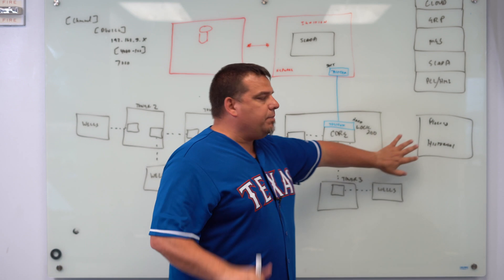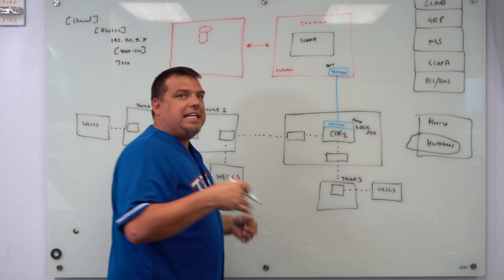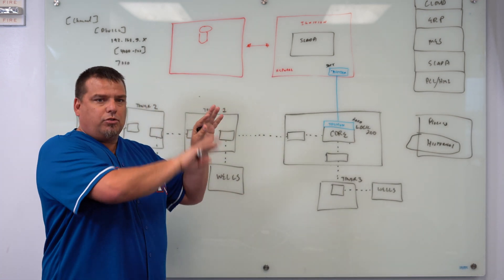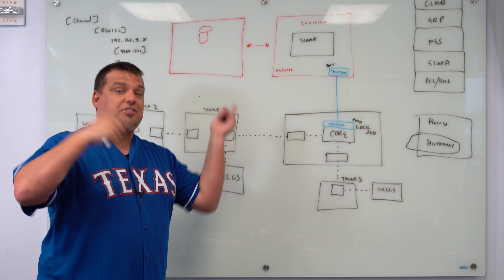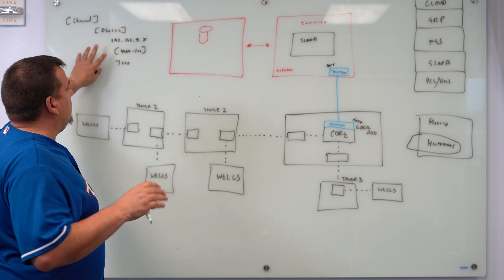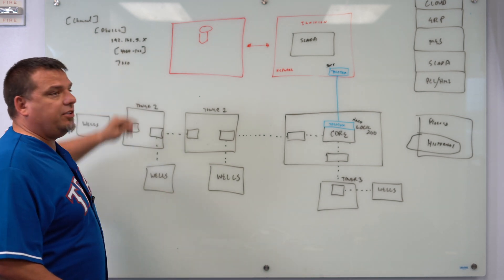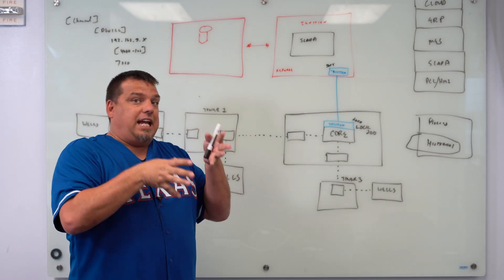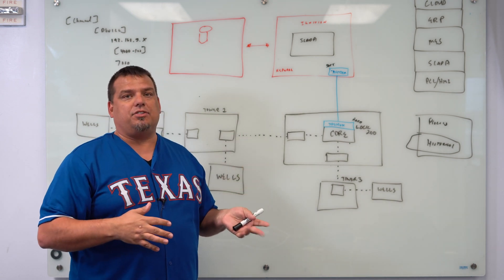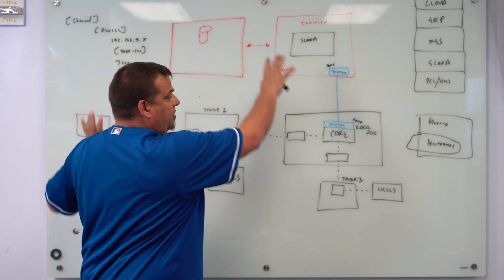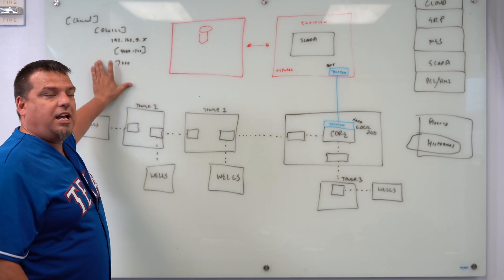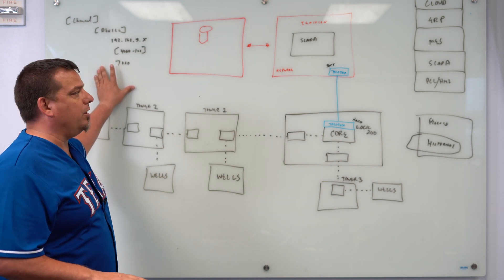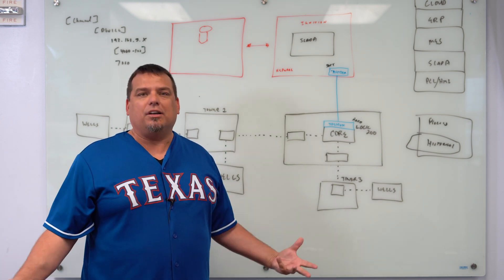When we're building out Kepware, we have to do the historical configuration - that's all the EFM data, in the EFM exporter. We have to create poll groups, and we have to put all 550 meters in the EFM exporter. We also have to configure all of the devices and all of the tags for the ABB total flow. That means we have to create channels, devices, and these configurations for literally all 550 wells. The fundamental difference between having the IIoT infrastructure in place and not having it is that we've spent the last three weeks or a month just doing the underlying infrastructure. Just mapping every single one of the wells into Kepware, just mapping all of the meters into the EFM exporter. Three weeks and something like 600 man hours has been spent just doing 550 wells.